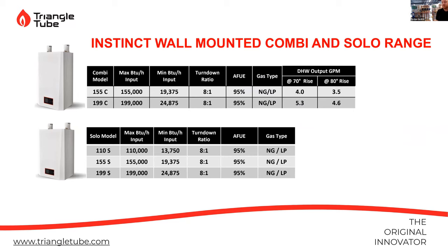Those come with system pumps. On the 155, our turndown ratio on all these boilers is 8 to 1. Max output in the 155 is obviously 155. Minimum is 19,000. The 70 degree rise, we get about 4 gallons per minute on the domestic. The 199, essentially the same thing, but we get 5.3 gallons per minute on the domestic.